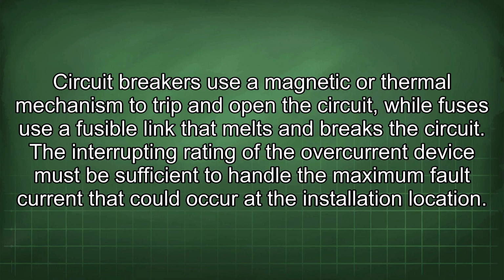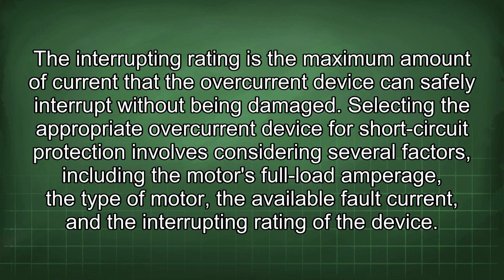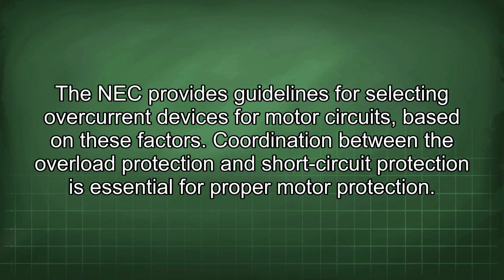The interrupting rating of the overcurrent device must be sufficient to handle the maximum fault current that could occur at the installation location. The interrupting rating is the maximum amount of current that the overcurrent device can safely interrupt without being damaged. Selecting the appropriate overcurrent device for short circuit protection involves considering several factors, including the motor's full load amperage, the type of motor, the available fault current, and the interrupting rating of the device. The NEC provides guidelines for selecting overcurrent devices for motor circuits based on these factors.